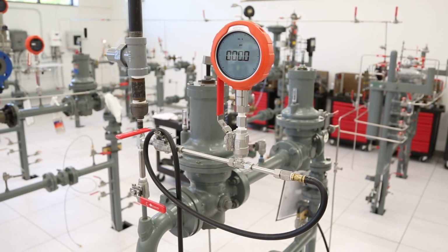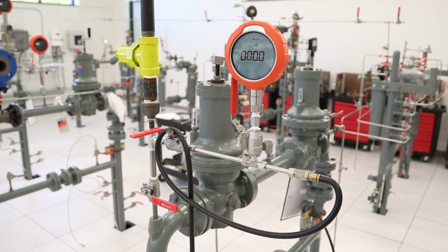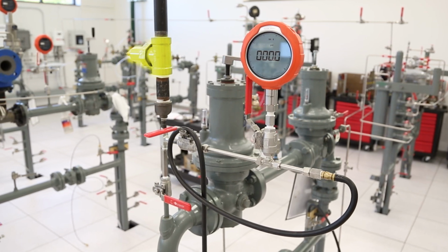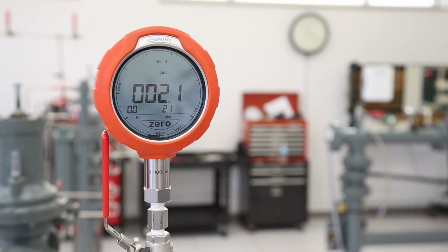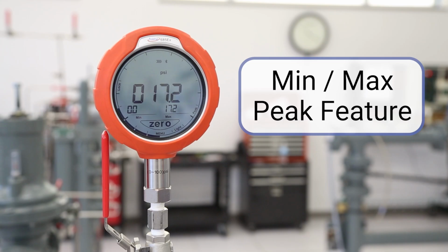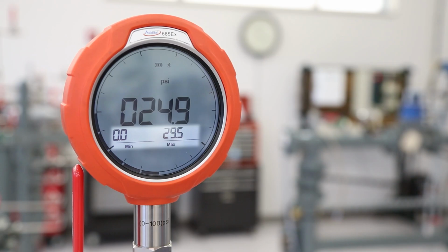But challenges in the field go beyond simple monitoring. The customer also frequently performed relief valve tests, where any pressure spikes must be recorded in a fraction of a second. Using the gauge's built-in peak feature, technicians can automatically capture the maximum pressure the moment the relief valve cracks, ensuring the system is working exactly as intended.